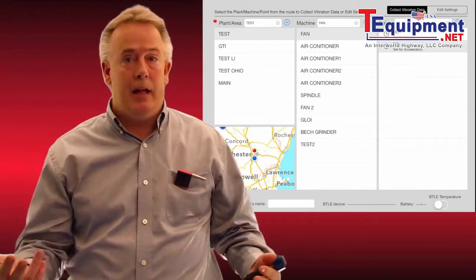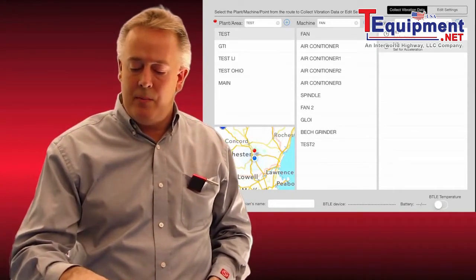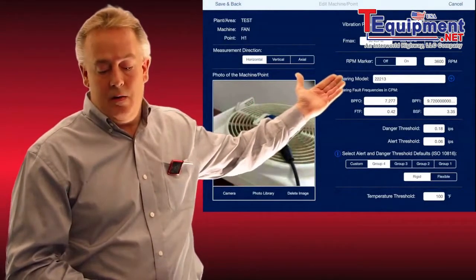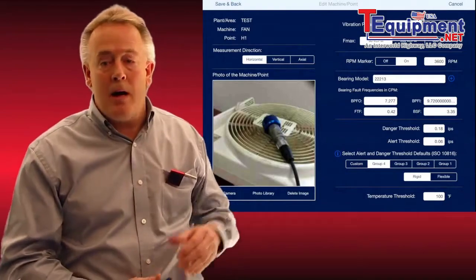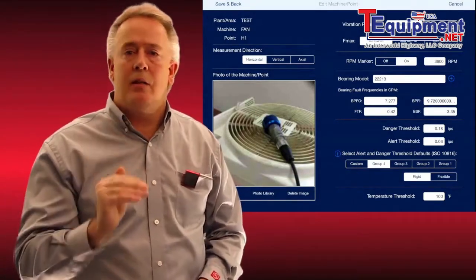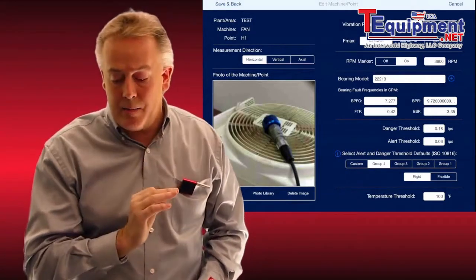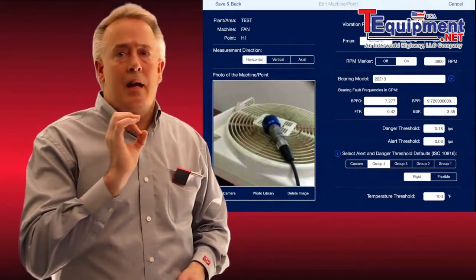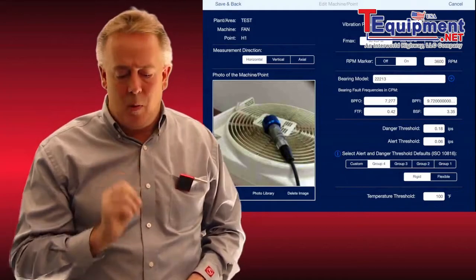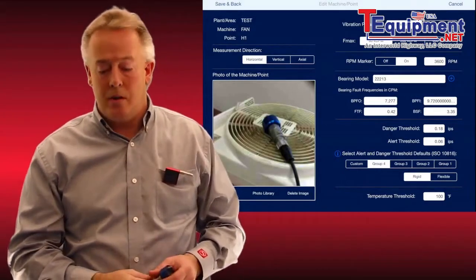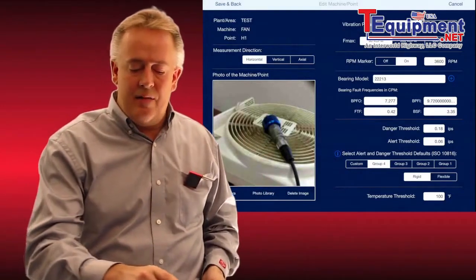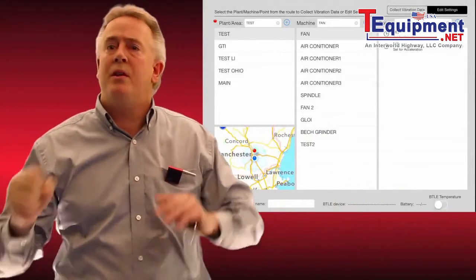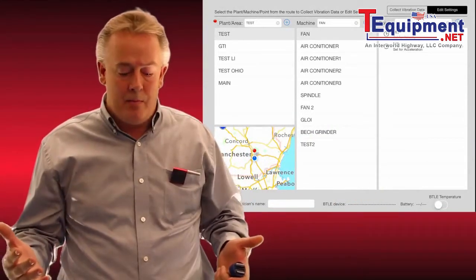If we need to edit a point or build that point, we simply hit the edit button at the top, tap on that same position. You can see I've got a photo of the asset point where the accelerometer goes, all my bearing models, and most importantly we have a danger and alert threshold that we can set for each piece of equipment or asset point. It isn't locked to ISO specifications, though there's a guide to help. We can dial in a specific danger level and alert level for each point, and also set whether we're in a vertical, axial, or horizontal position. We hit save and back, and that route is permanently set — we configure it once and we're done.